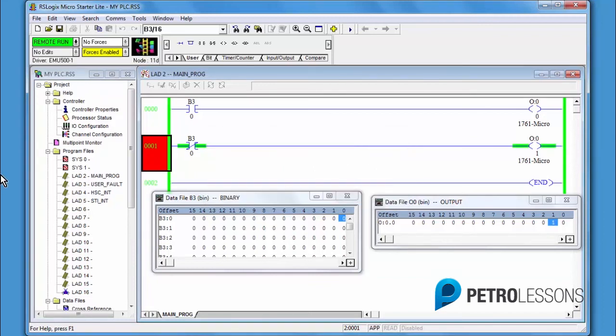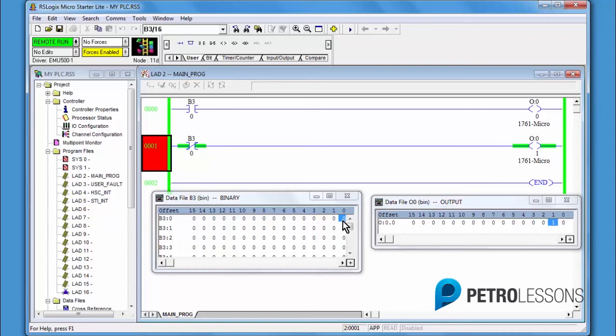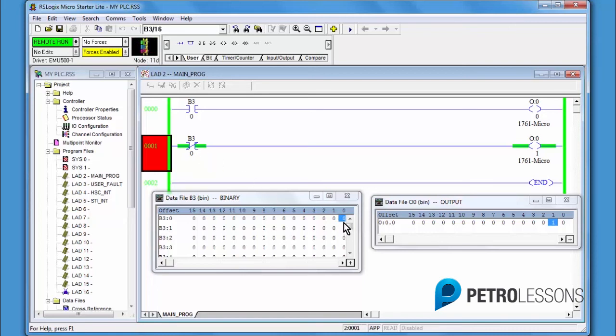In rung 0, 0, 0, the XIC is looking for a 1 to be on. The data table shows a 0, therefore the XIC is false. In rung 1, the XIO is looking for a 0, an off condition. The data has a 0 and the bit is off, therefore it satisfies the condition for the OTE, and the OTE will be on.